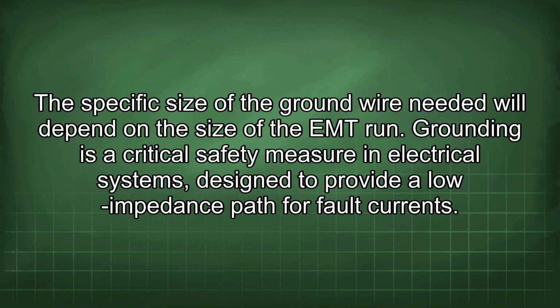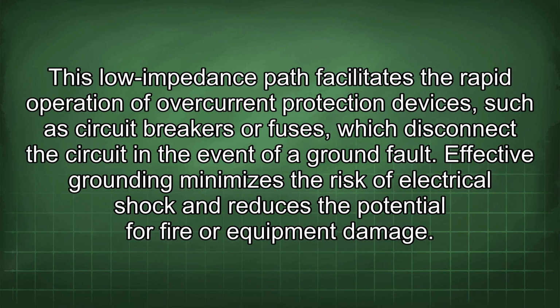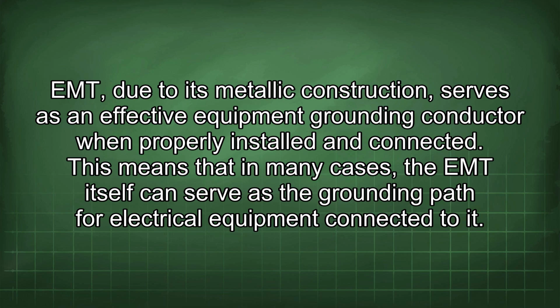Grounding is a critical safety measure in electrical systems designed to provide a low impedance path for fault currents. This low impedance path facilitates the rapid operation of overcurrent protection devices, such as circuit breakers or fuses, which disconnect the circuit in the event of a ground fault. Effective grounding minimizes the risk of electrical shock and reduces the potential for fire or equipment damage. EMT, due to its metallic construction, serves as an effective equipment grounding conductor when properly installed and connected. This means that in many cases, the EMT itself can serve as the grounding path for electrical equipment connected to it.